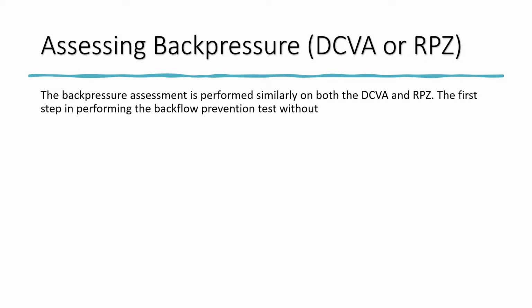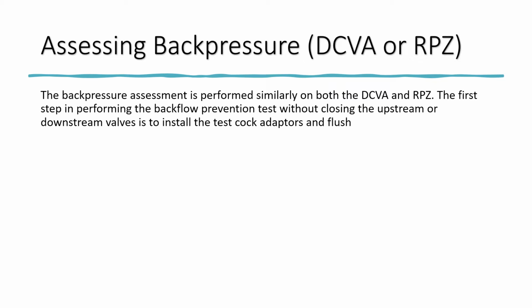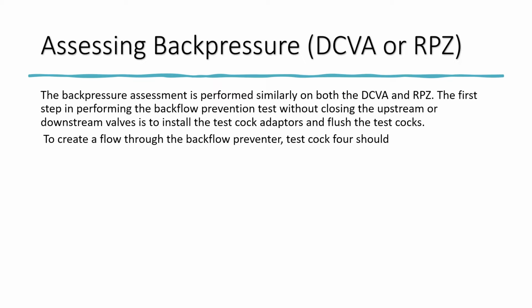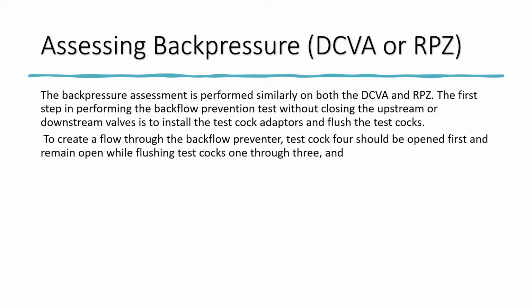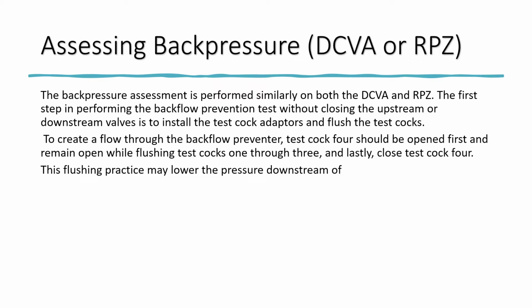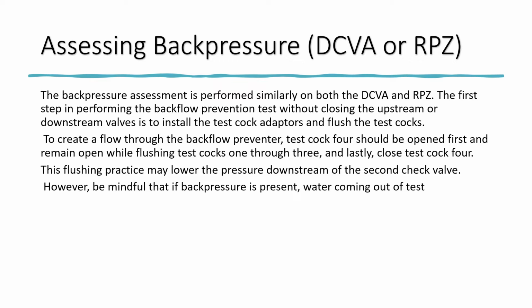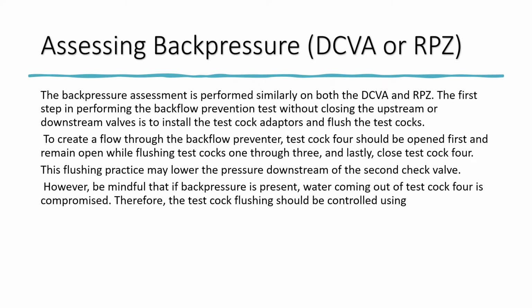The first step in performing the backflow prevention test without closing the upstream or downstream valves is to install the test cock adapters and flush the test cocks. To create a flow through the backflow preventer, test cock 4 should be opened first, and remain open, while flushing test cocks 1 through 3, and lastly, close test cock 4. This flushing practice may lower the pressure downstream of the second check valve. However, be mindful that if back pressure is present, water coming out of test cock 4 is compromised. Therefore, the test cock flushing should be controlled using a clear plastic hose and a suitable receptacle.